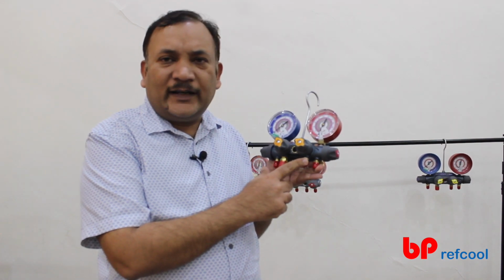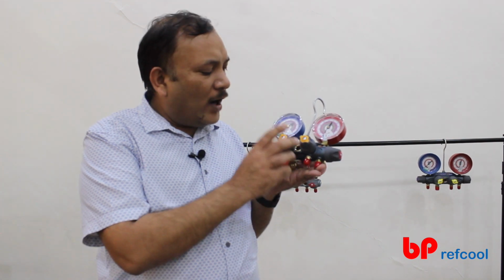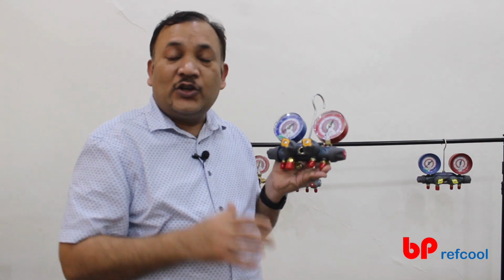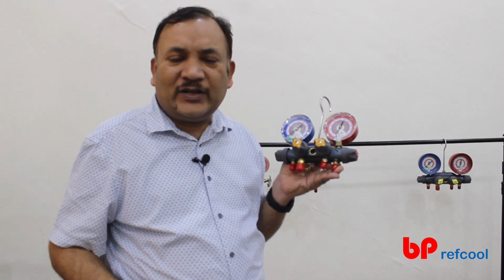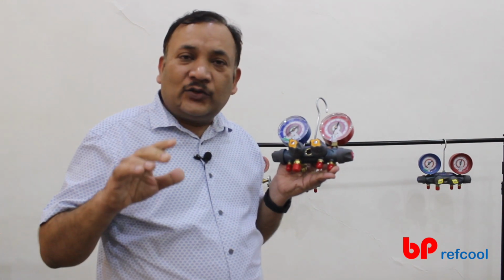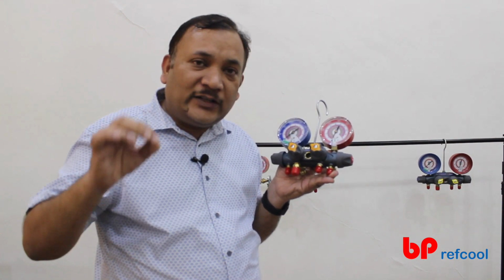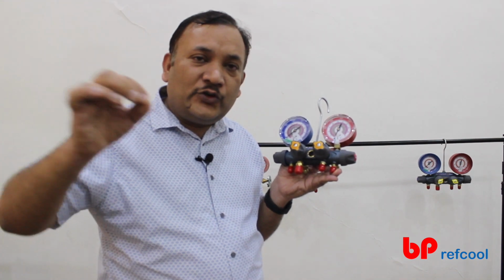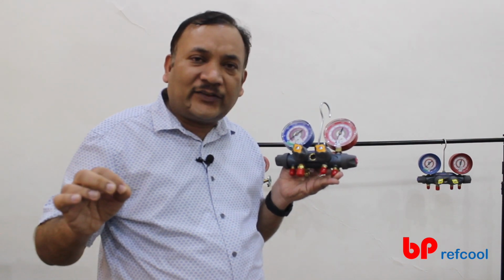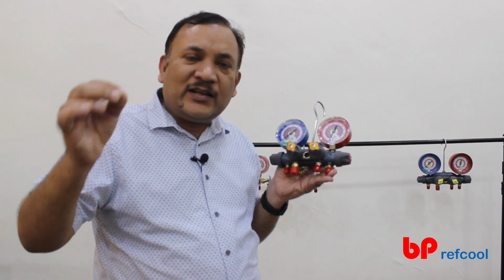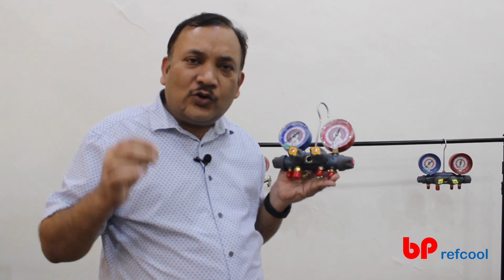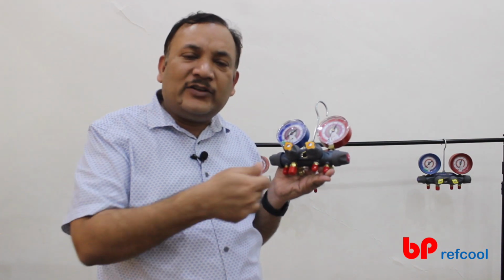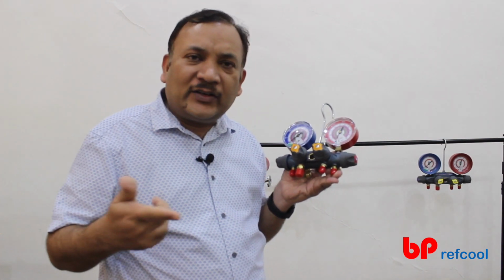This is something which you connect to the refrigerant cylinder. Now what happens in this typical case, you directly connect both the vacuum pump as well as the refrigerant gas cylinder. So essentially what you're doing is you're vacuuming till the cylinder. So you don't need to change any hose while doing the gas charging. So there is no refrigerant gas emission going to happen, and there is no chance of air getting added when you are changing the hose and doing the purging and all that stuff after the vacuuming. So in this case, this gives you a complete control of the system.